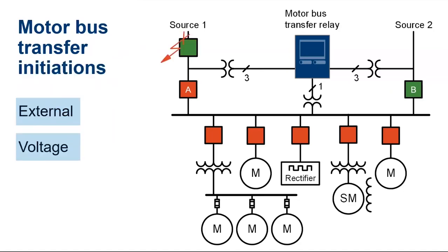There are two types of bus transfer initiation. External initiation could be from an external source like an upstream relay transfer trip scheme, and it can be caused by an overcurrent element or an undervoltage element. The other one is voltage initiation from an internal undervoltage element setting. So loss of voltage could be something as simple as an upstream breaker mistakenly being open.